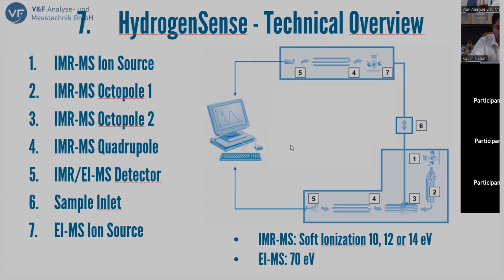So what we use this part of the spectrometer for is the very low concentrations. And the EIMS is mainly used for the inert components. So it's used for argon, for helium, and for nitrogen, which also in the regulations are allowed at a much higher level of 500 ppm or 300. I'm not sure about the latest release that they brought out. So these ones will be used only for 3 components, and the IMRMS spectrometer will be used for all the rest that we need in order to produce the signals that are regulated in these 2 documents.